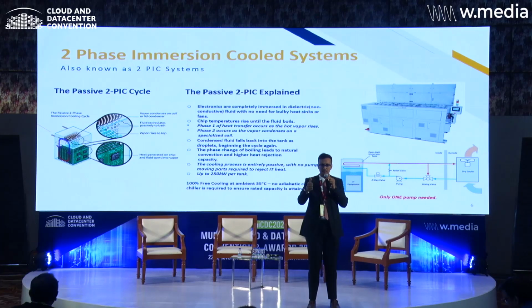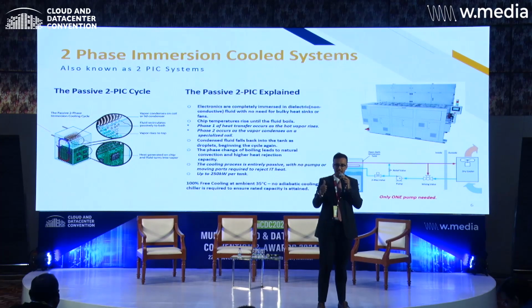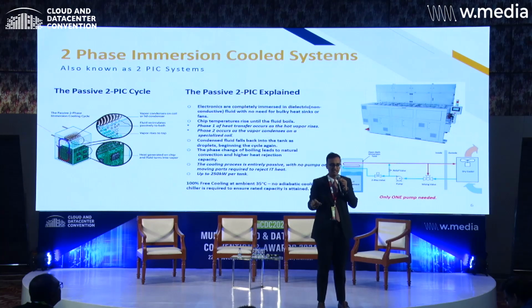Just to put it in numbers, if you have to design a 30 megawatt data center, you can do the entire setup of the data center with all the services in ground plus 2 floors, compared to an air-cooled data center which would take ground plus 6 or 7 floors to set up. There are also CapEx savings today on two-phase immersion cooling.